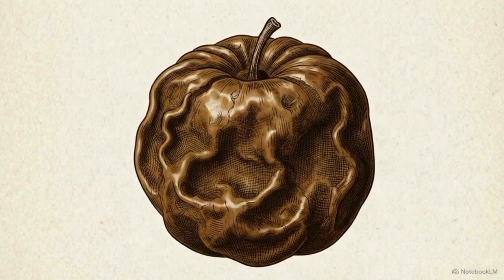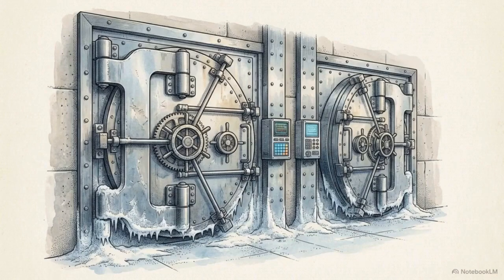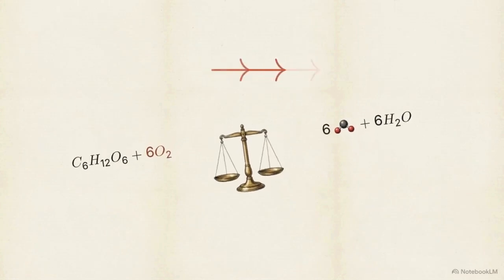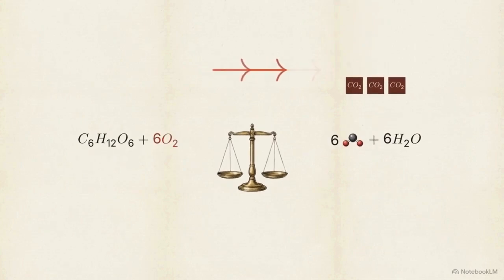Controlled atmosphere, or CA storage, is the engineering solution used to break this autocatalytic loop. We can view aerobic respiration through Le Chatelier's principle. Changing the concentration of a chemical component shifts the system's equilibrium. By artificially reducing the ambient reactant, molecular oxygen, engineers force the chemical reaction to slow down. They simultaneously pump the ambient environment with excess product, specifically carbon dioxide. An abundance of external carbon dioxide creates back pressure against the equation, further stifling the fruit's ability to respire.